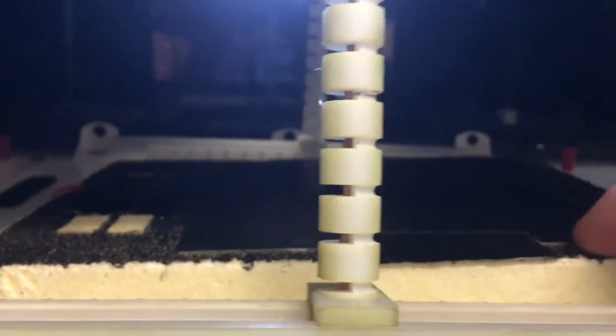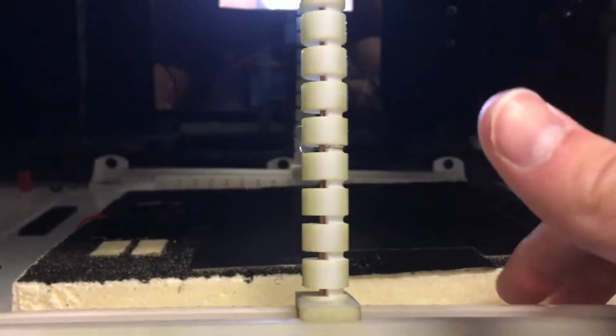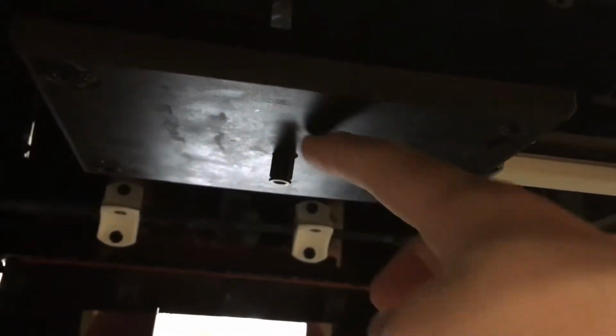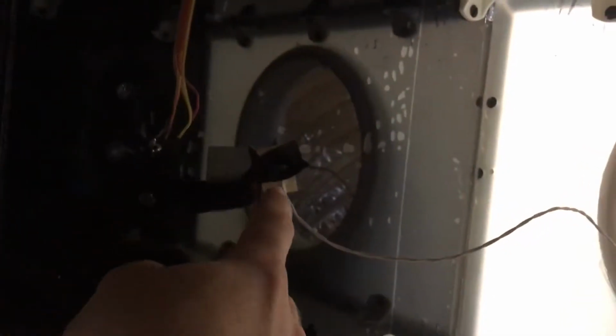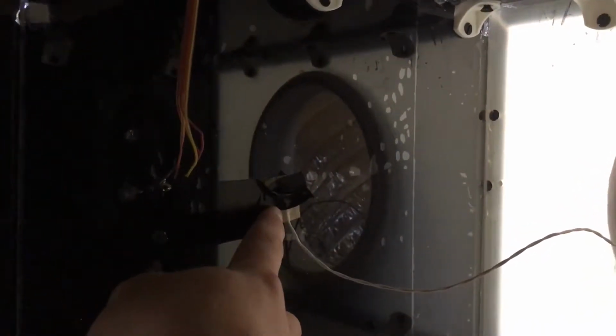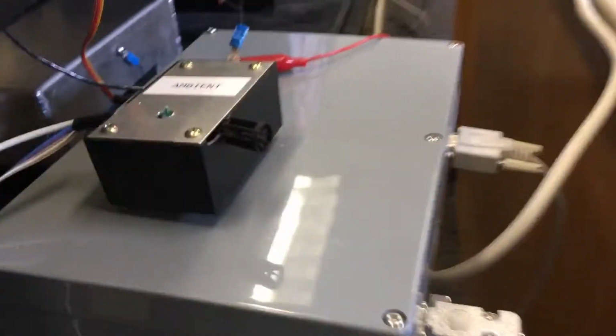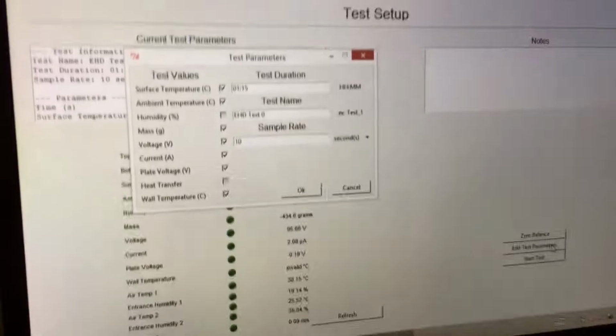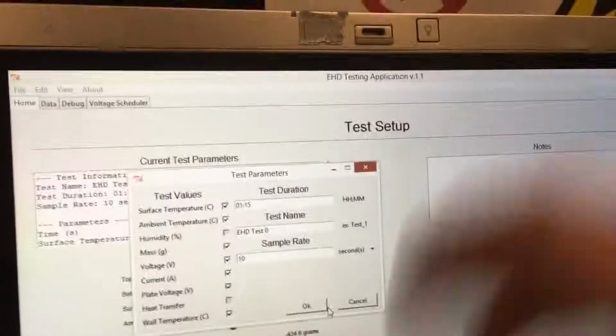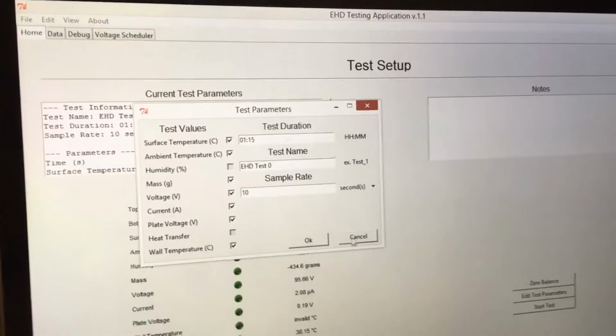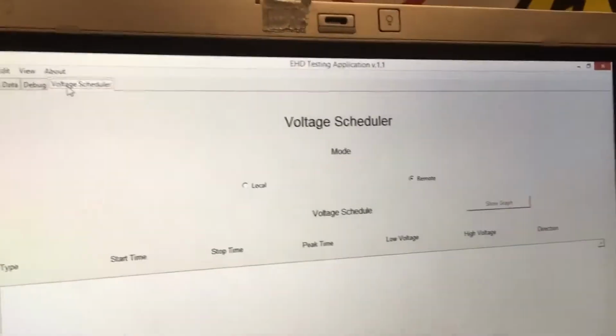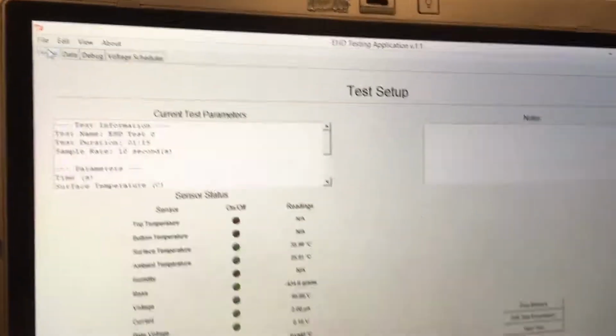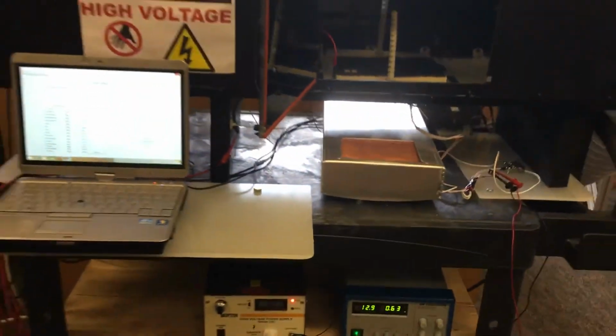That would take all the readings from the thermistor underneath the hot plate, the thermistor underneath the polystyrene foam, the infrared sensor, the surface temperature thermistor, and then the ambient temperature sensor over here. It takes all those values to calculate the heat transfer coefficient, and then so again, you would set up your test by test duration, test name, just like before, click OK, do your voltage scheduler, just like before, and then you are able to run a heat transfer test.